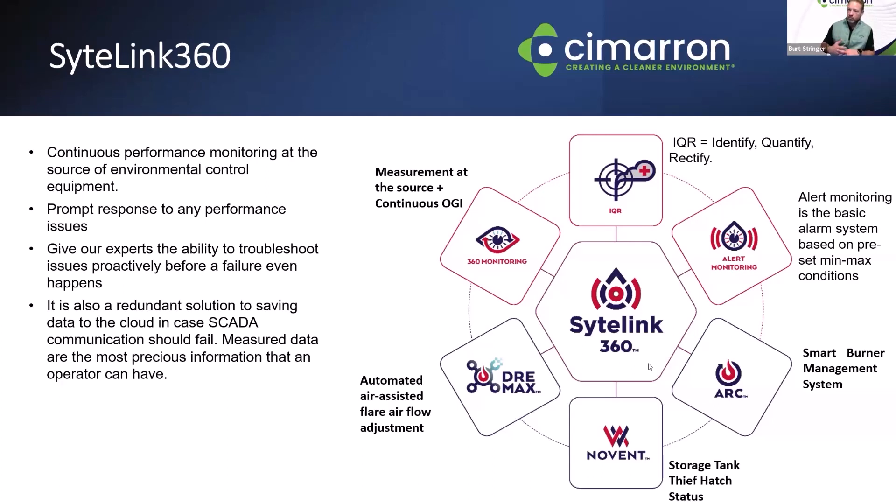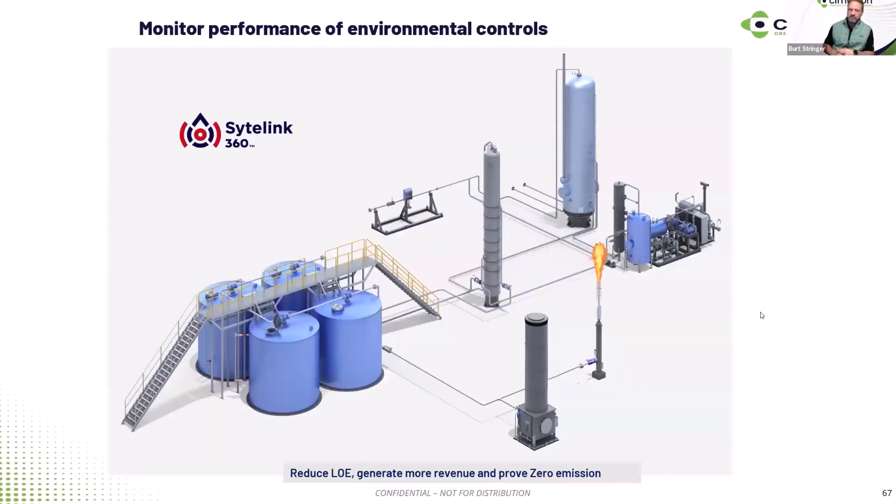Via the DRE MAX, we're taking the real-time data back from the system and making those adjustments to ensure we're achieving 98-plus percent destruction efficiency. The same goes for tanks and VRUs — monitoring the tank pressure and flows coming in so you can remotely adjust those set points to make sure you're capturing as much gas before you combust, definitely reducing and eliminating those pop-off events that lead to super emitter type events.